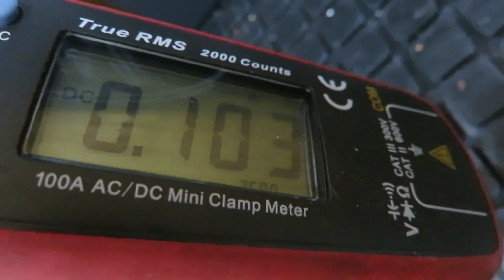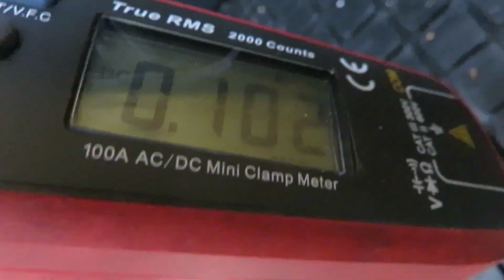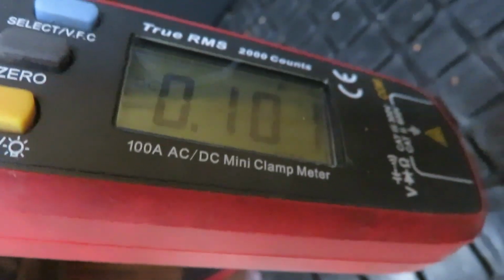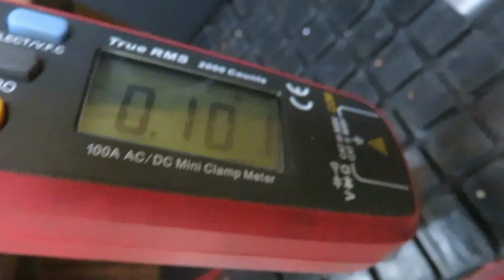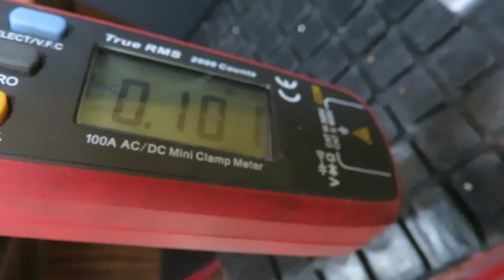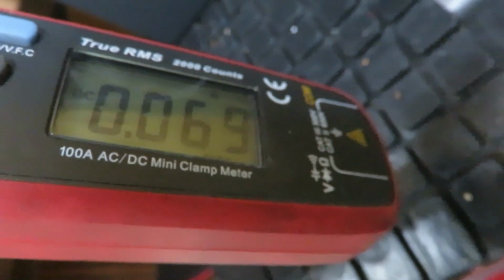I'll turn the button off on the inverter - it should go to zero. It doesn't go to zero, which means it has a load. I'll turn the breaker off. Now we're not zeroed out, so let's try the zeroing out thing again.